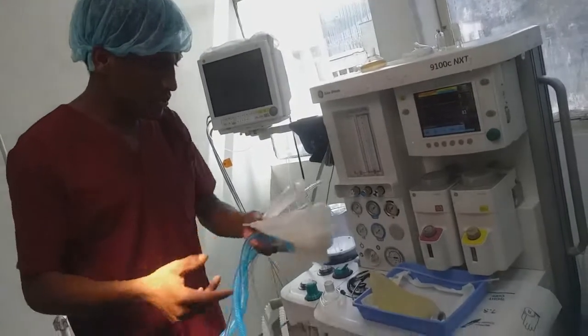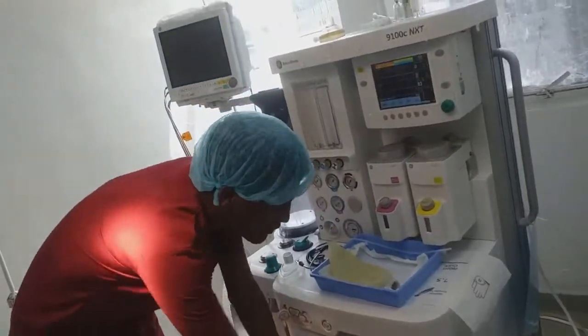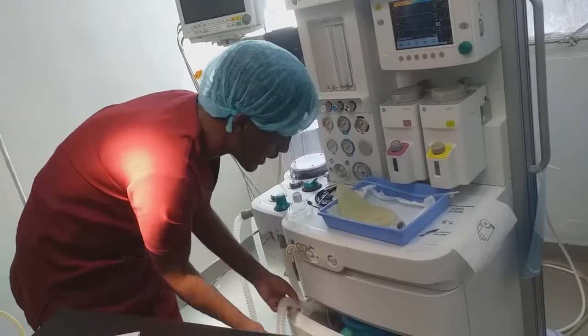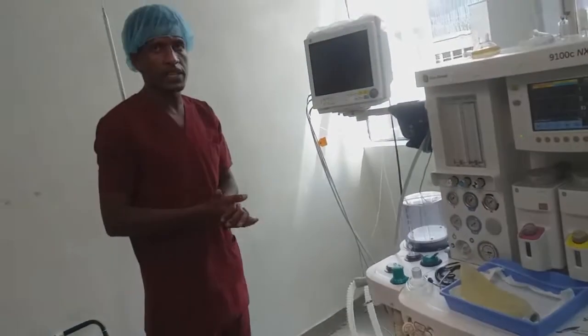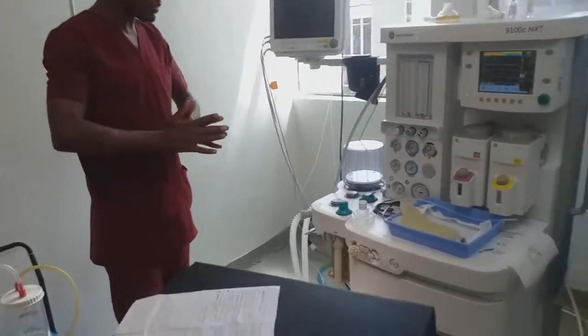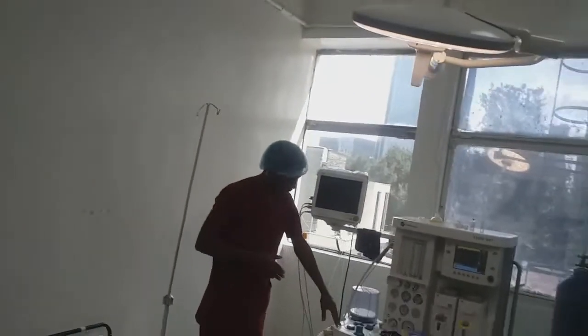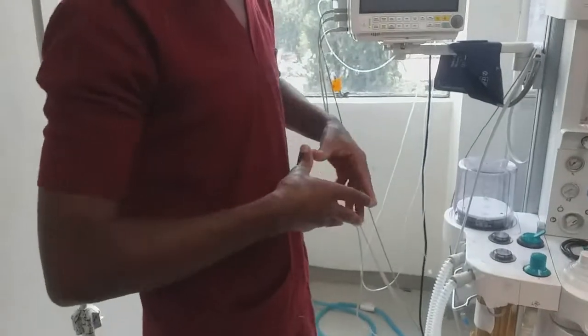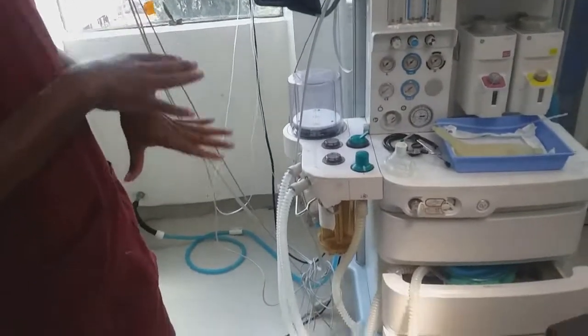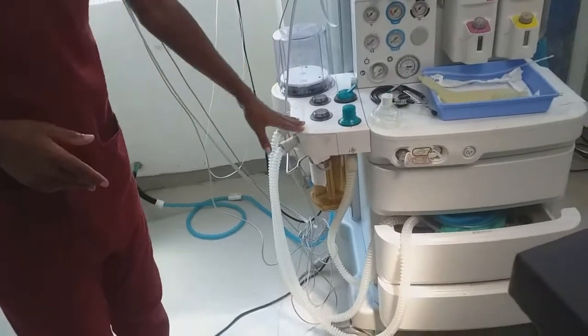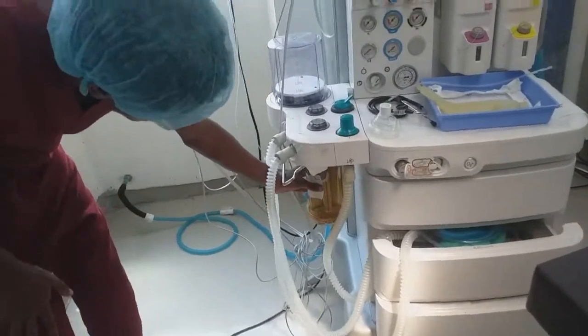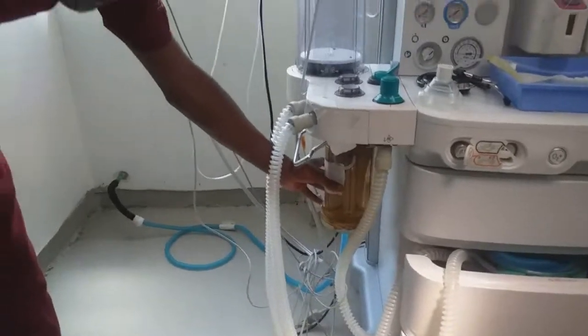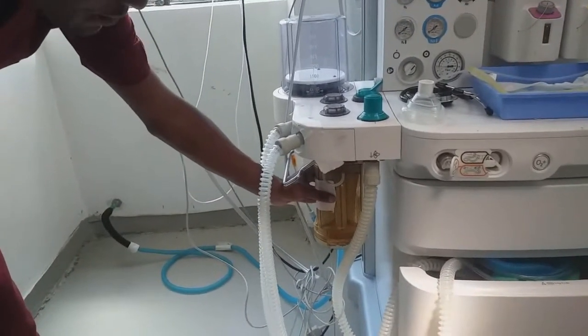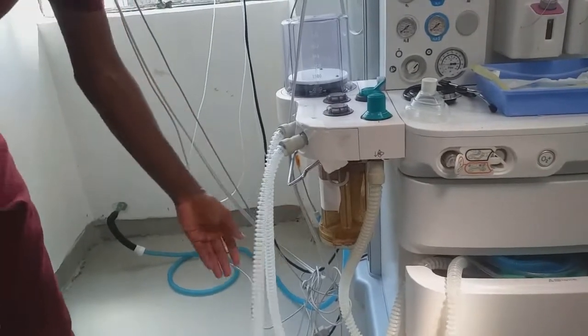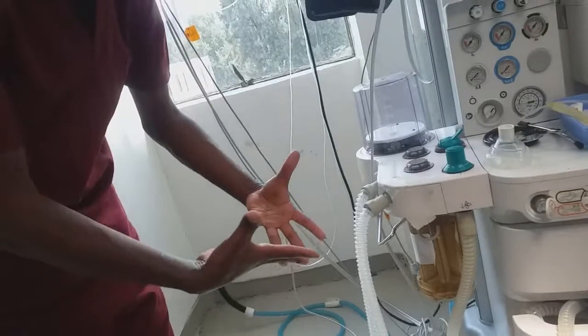In anesthesia machine, we also have a rebreathing preventer. Rebreathing prevention means there is a means of carbon dioxide removal in the anesthesia machine. This is what we call the canister. The canister has soda lime, which is used to remove carbon dioxide.